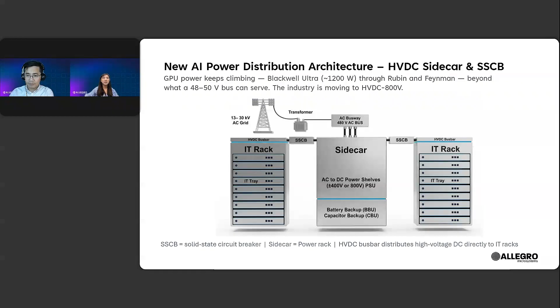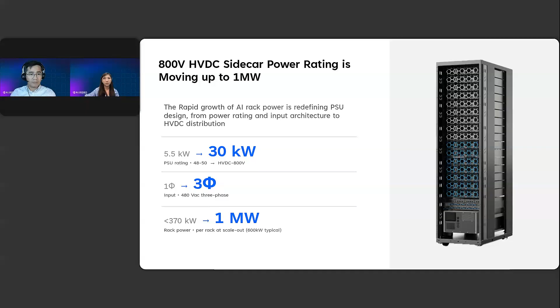So let's see how this shapes PSU design. The key trend is clear: as AI computing power continues to increase, rack power also keeps moving higher. The HVDC migration also changed the PSU design. At 800 volt, the PSU needs to handle higher voltage stress, higher isolation requirements, and more complex topology. We also see the PSU power rating moving from lower power levels to around 30 kilowatts and beyond, with three-phase input. So 800 volt is not only a bus voltage change, it's a full power architecture migration, and this migration creates new design challenges inside the PSU.